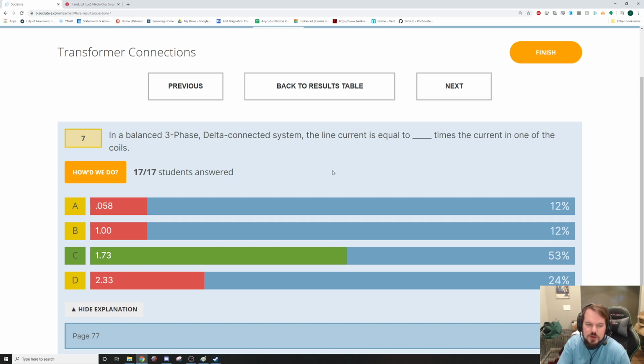The difference between different wiring methods for a three-phase transformer - there's Y and delta. Delta is what we just talked about, it has current times 1.73. And Y, it's voltage times 1.73.